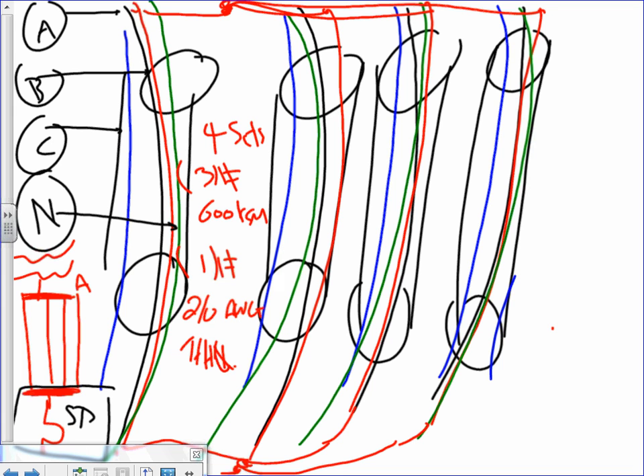All of them are THHW. Anybody know why we use THHW? Well, if it's service that's coming from outside, typically when they go underground, you need a conductor with a W. What does W stand for? Wet. Yep. Can I use THHN coming from outside? Not legally, no, you can't use THHN. THHN is only for indoor, dry locations. Wet location, you need one with W at the end of it, like THHW.